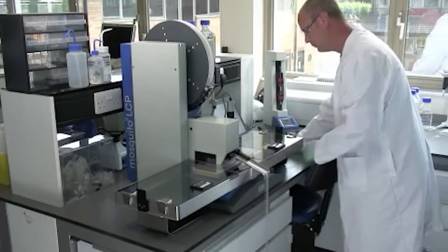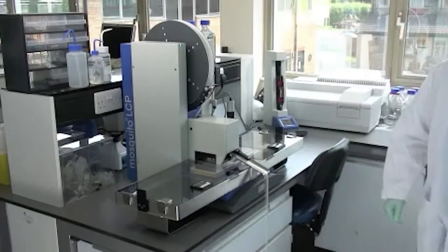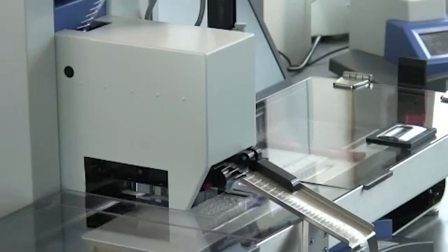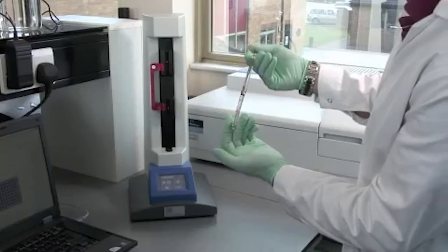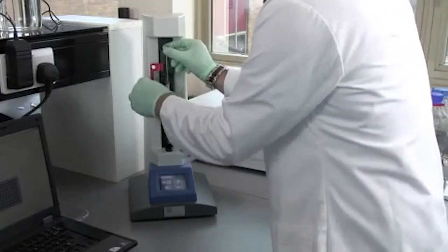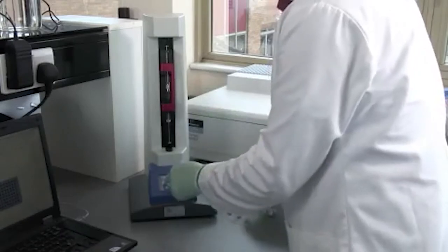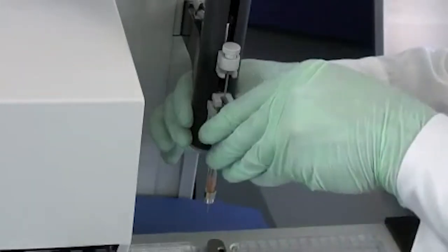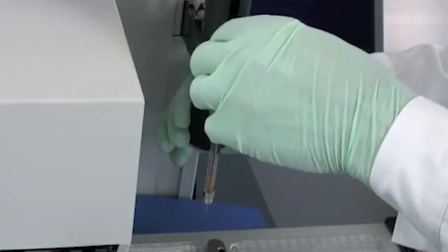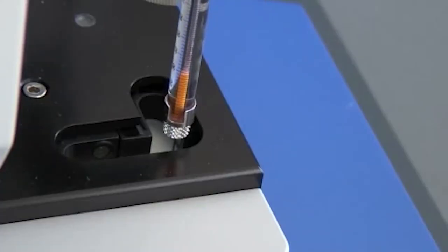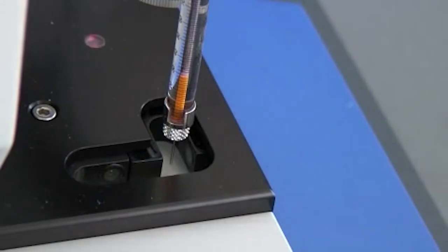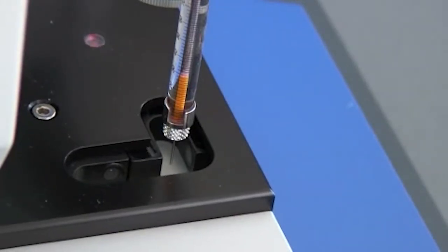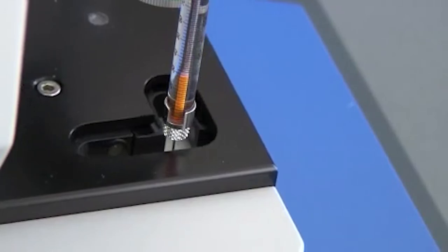Mosquito LCP is an extremely fast and robust simple to use instrument that automates what was previously an extremely difficult process. As part of the collaboration we realized that there were some peripheral elements to LCP sample preparation that we could help with. So we also developed an automated benchtop mixer and from there we take the syringe of the mixed LCP solution, add a dispense needle and then use the change syringe wizard in the software to load the syringe onto the instrument extremely quickly and easily. We then use an auto-calibrate feature which references the point of the needle tip for that specific syringe full of LCP.